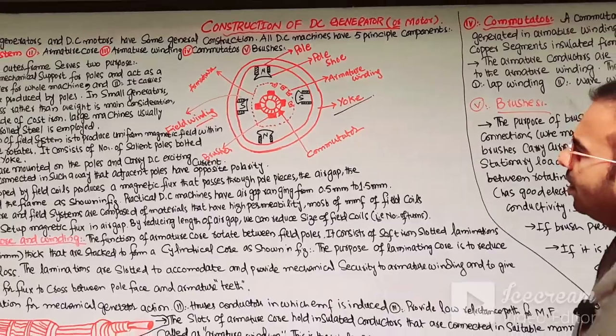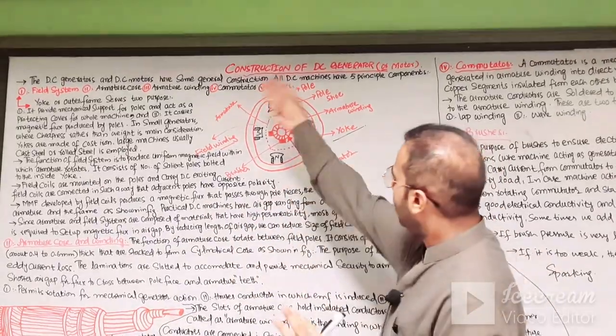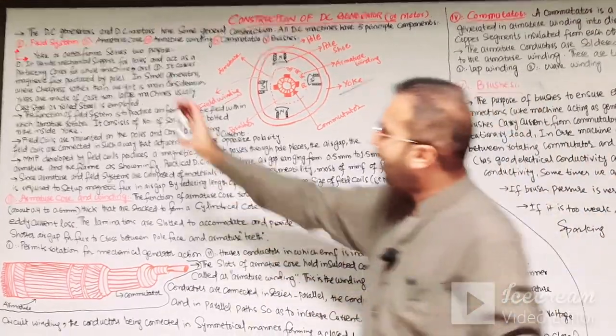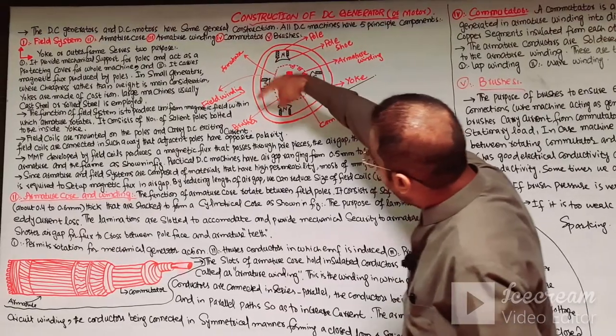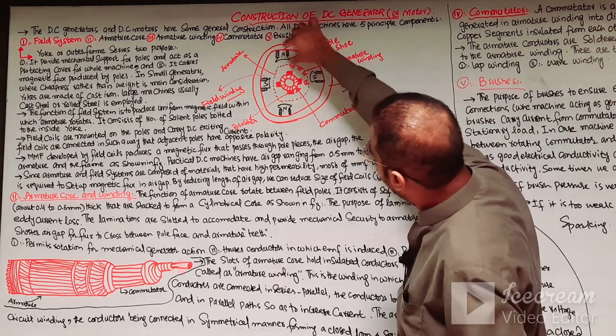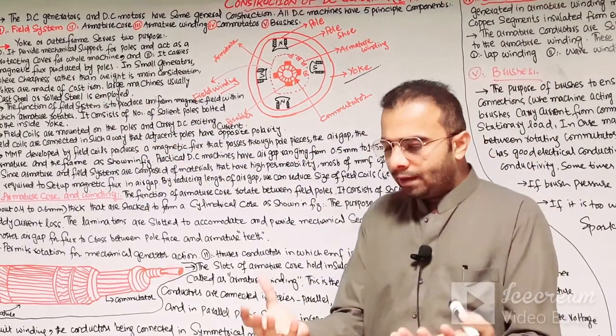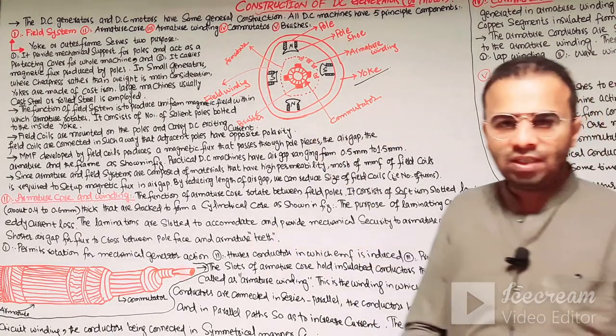The yoke or outer frame serves two purposes. First, it provides mechanical support for the poles and acts as a protective cover for the whole machine. Second, it carries the magnetic flux produced by the poles. These poles carry DC exciting current through the field coils, and the purpose is to carry the magnetic flux produced by the field winding.